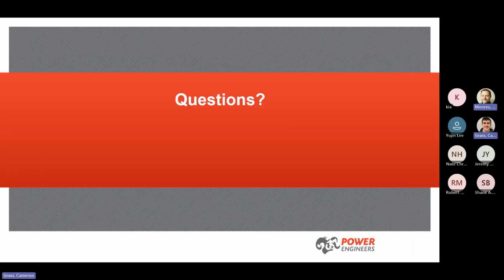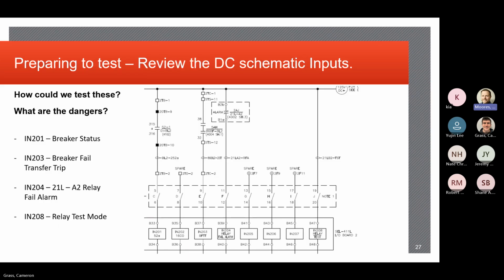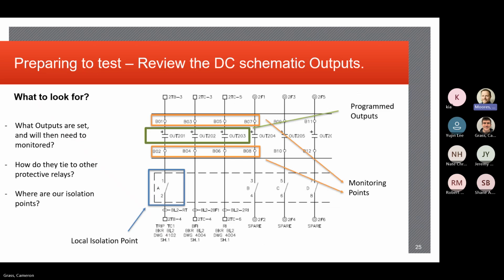Yeah, I think the point is, looking at all the I/O, you want to make sure you're testing all of those things. From a relay perspective, you're testing from the test switch in, right? In that case, these are inputs. In the previous case, or test switch out for the outputs. Or no, I guess that would still be in, right? And we're using those test switches, and we're testing all of the used outputs and the logic associated with it.